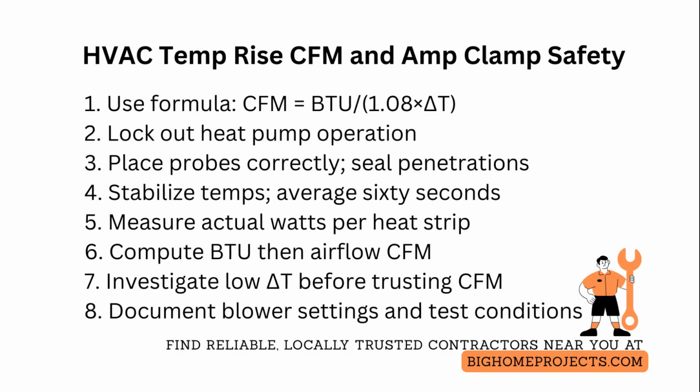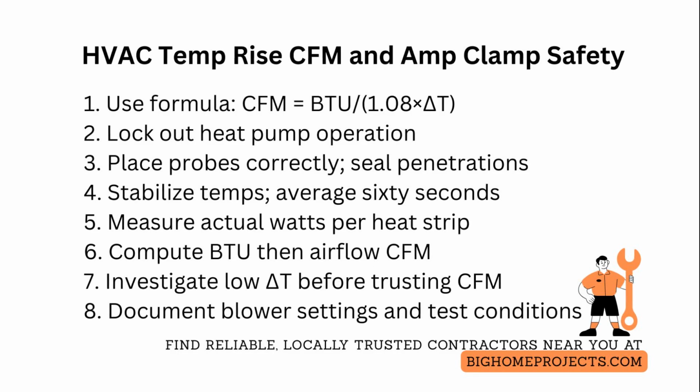Put the system in heat strip mode only and confirm outdoor units are locked out, so you are not mixing heat pump capacity with electric strip heat.